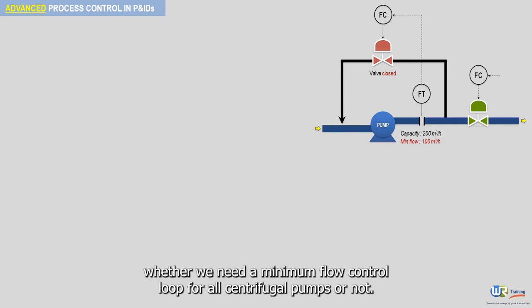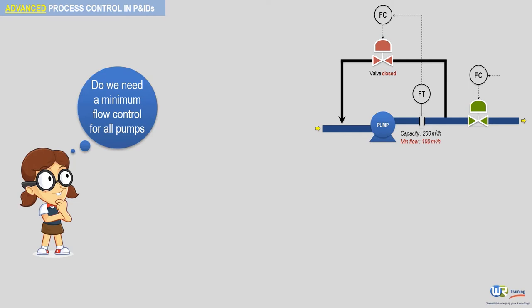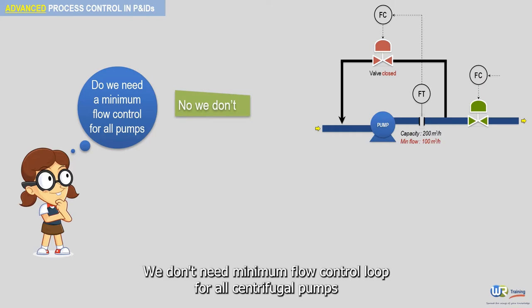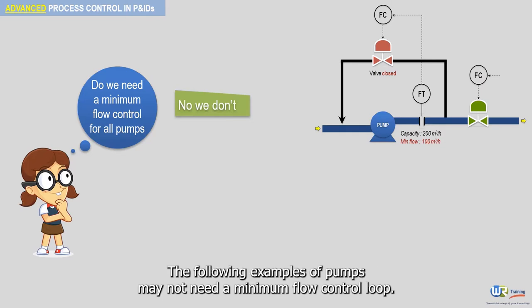The question is whether we need a minimum flow control loop for all centrifugal pumps or not. The answer is no. You will not see this type of control on each centrifugal pump at your facility. We don't need a minimum flow control loop for all centrifugal pumps.